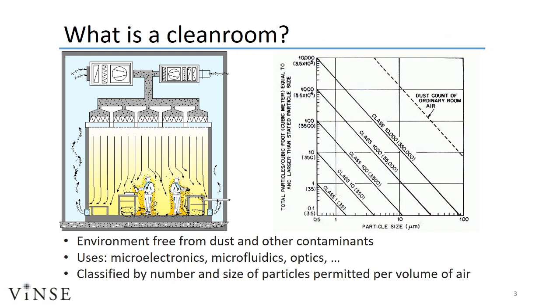The air quality is monitored throughout the clean room, which is maintained through a number of methods, primarily air filtration. The air in the clean room is pushed through HEPA and ULPA filters located just above the ceiling tiles of the process bays. This creates a laminar flow from the ceiling to the floor, carrying contaminants with it through the floor vents, where it will undergo further refiltration or forcing them to settle on the floor, where they can be vacuumed or tacky rolled.